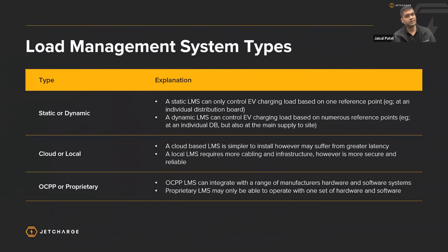So there's a few different types of load management systems. For example, they're lumped together as either a static or a dynamic load management, where a static load management can only control an EV charging load based on a single reference point. So you set a limit on the EV charging for that site and the chargers will never exceed that limit.